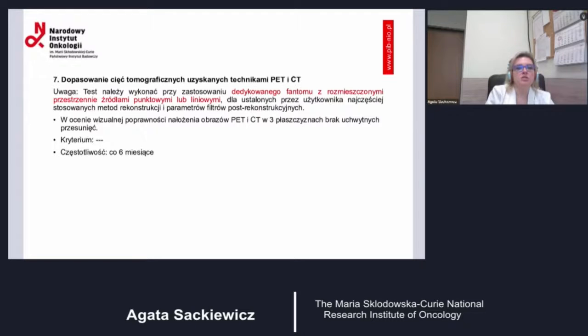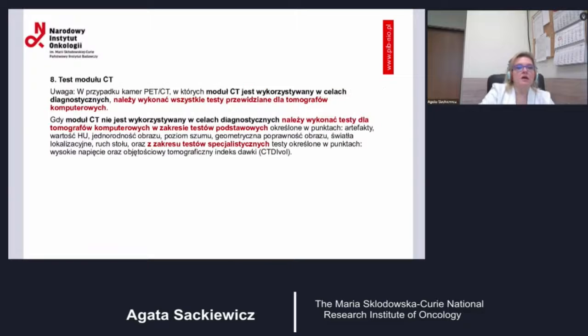This test should be performed using a dedicated phantom with distributed spatial point or line sources, using reconstruction methods and post-reconstruction parameters. Here we are looking again at the guidelines of the manufacturers, which should make clear how to perform such tests for the fusion images, for nuclear medicine and tomographic tests. We should assess three planes, and I have already mentioned that it should be done every 6 months.